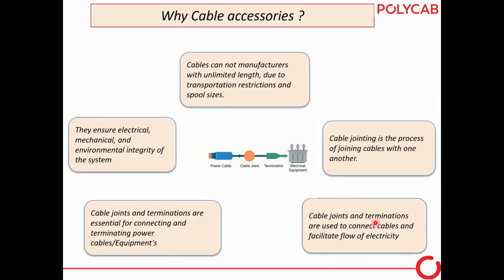So let's see why cable accessories are actually required. If it is so important, the basic question comes: why are cable accessories required? Because anyone wants to avoid cable accessories. If we got cables kilometer to kilometer in length, why should we use joints? We could directly use the termination. So let's see why cable accessories are required. First, we cannot manufacture cables in unlimited length. We have a restriction because of the spool length and transportation. So we cannot manufacture cables kilometer to kilometer.